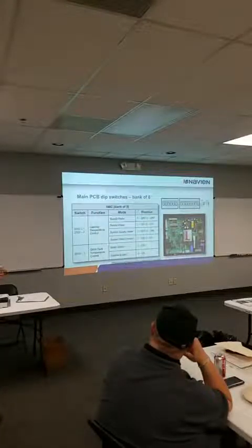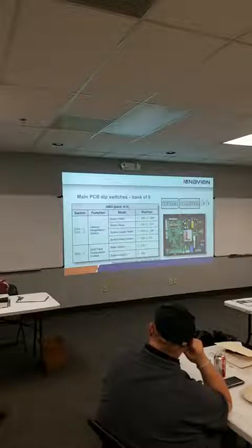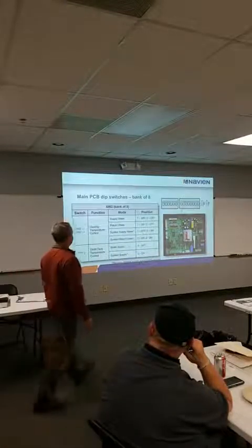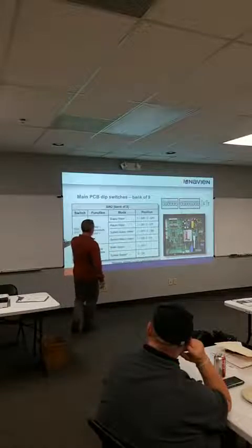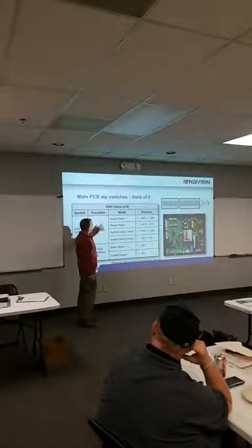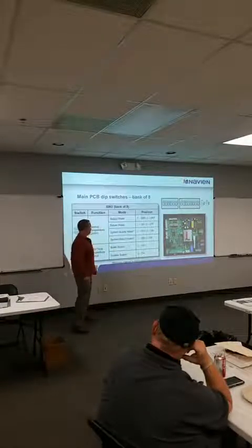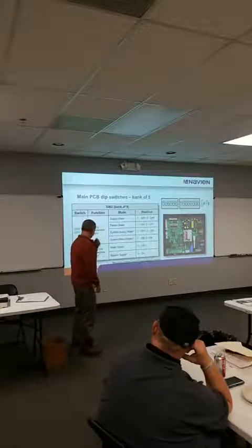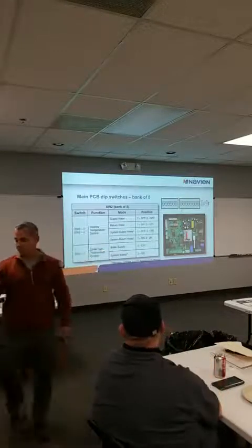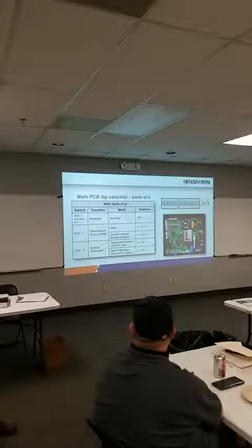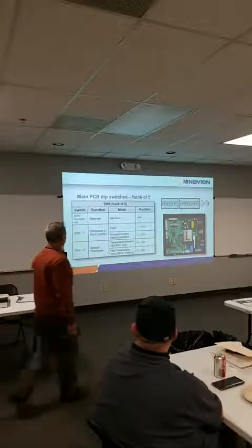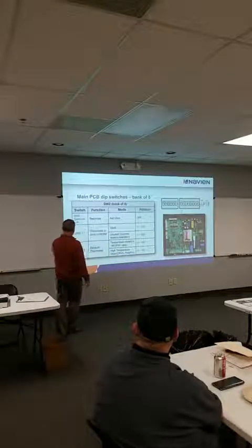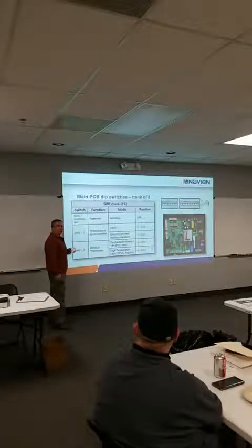So, these are the dip switches. This is gonna be identical to every unit that we have with this board. So on your original board, your dip switches are gonna tell the unit what it's doing. They're gonna run return or supply water on that system. And then if you're using a thermostat, number 8 dip switch is important because from the factory, we limit exhaust temperature to 149, so we're always condensing.